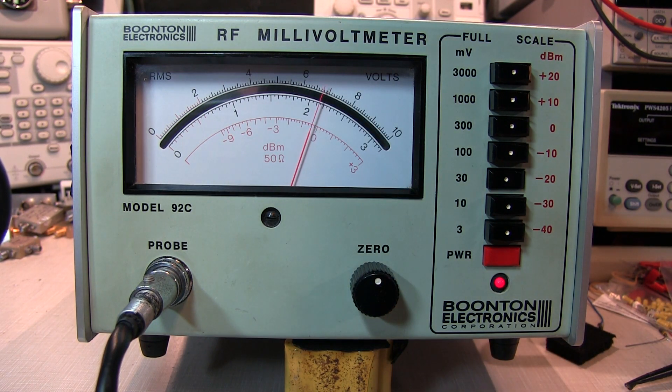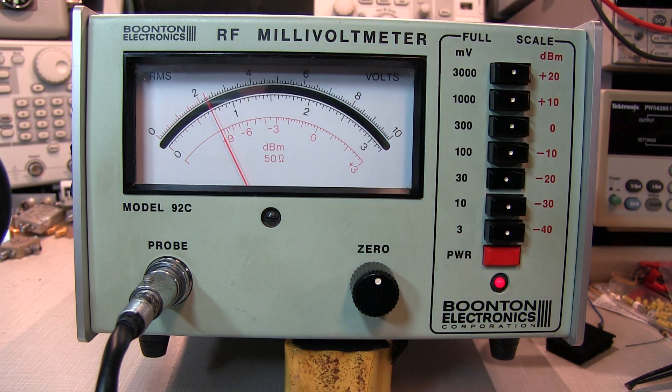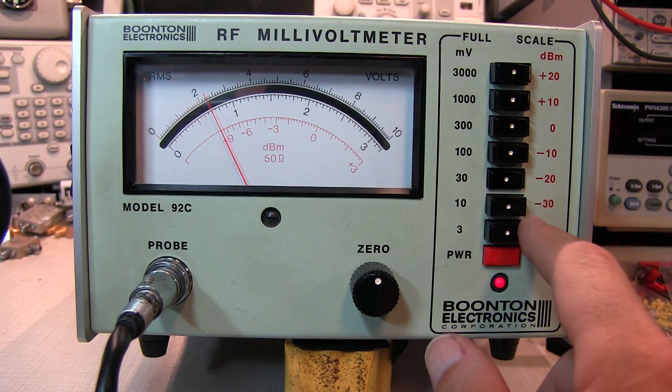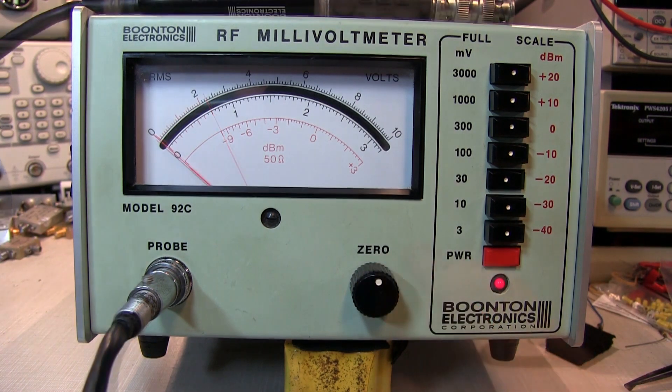And we'll go down another 10 dB. So there's minus 21, 22, 23, and I work my way down to minus 30 dBm. Now before I switch to minus 30, the lower two scales on this meter actually have a zero adjustment.